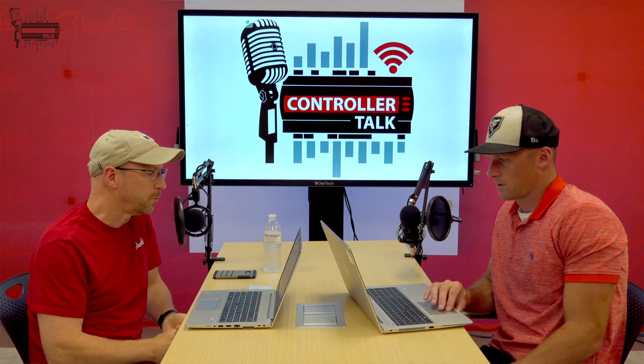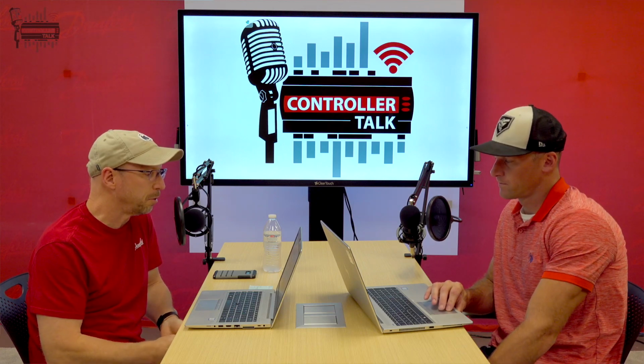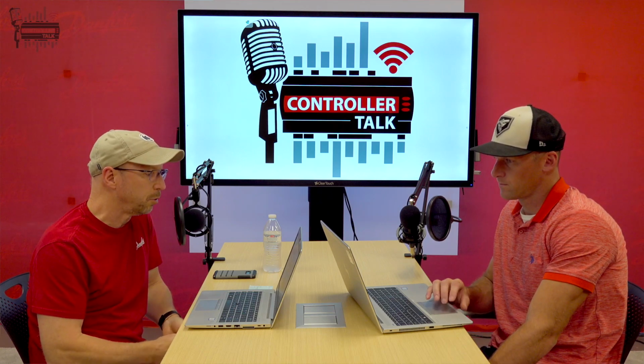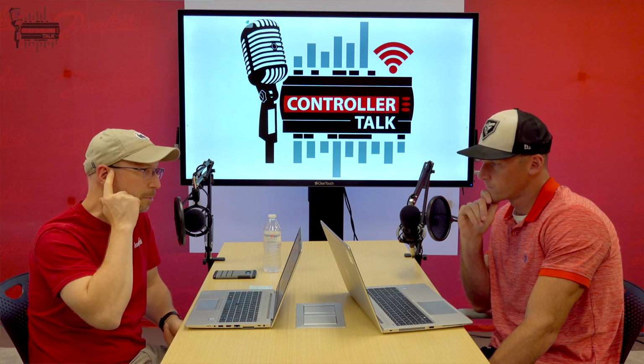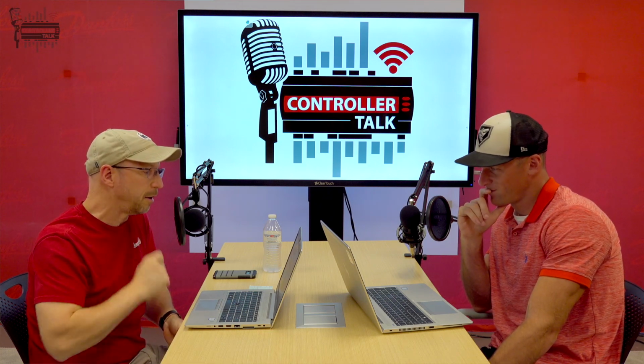But yeah, there is that distance limitation on this model. All right, and as far as power supplies go, then you can run 24 volts AC or DC over to the pack controller. And if you have multiple extension modules plugged in, you want to start adding up the VA ratings. And you want to stop when you get to 32 VA, which is quite a bit. Yeah. And that's a long set of boards.